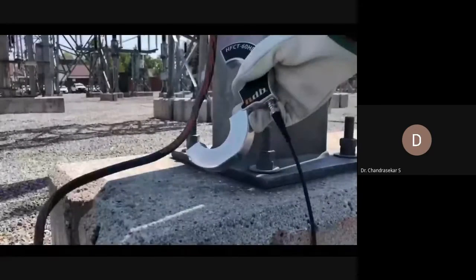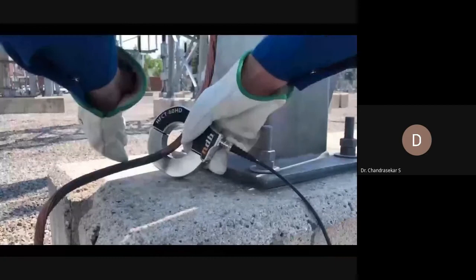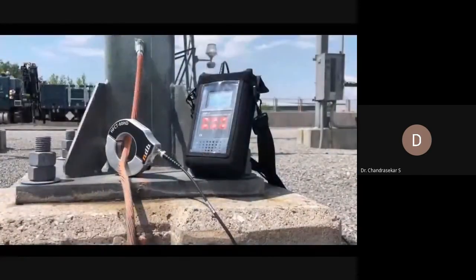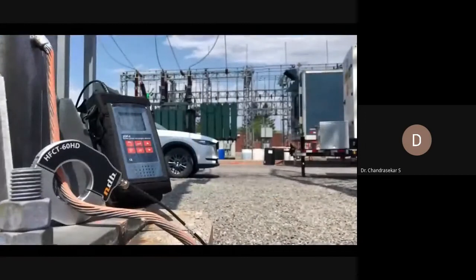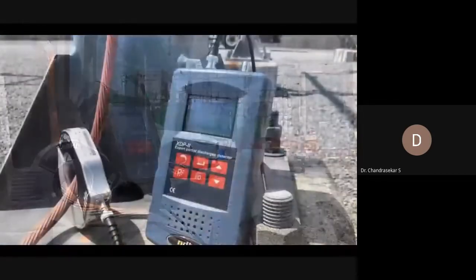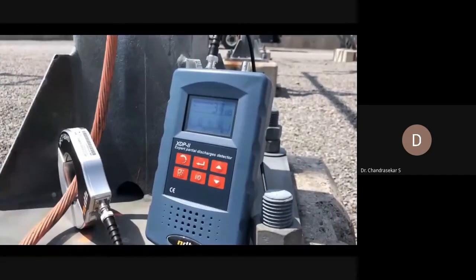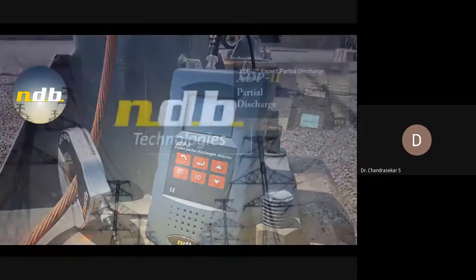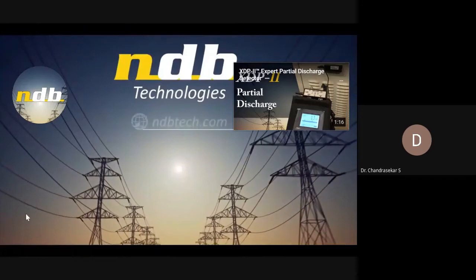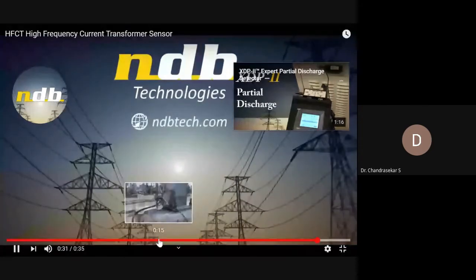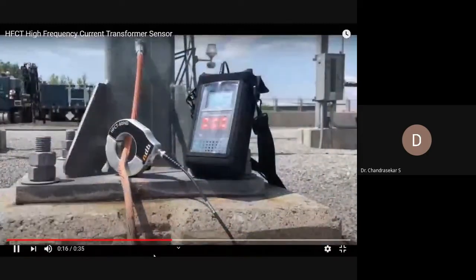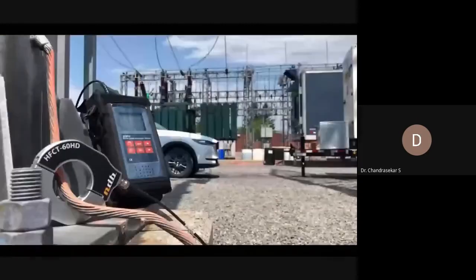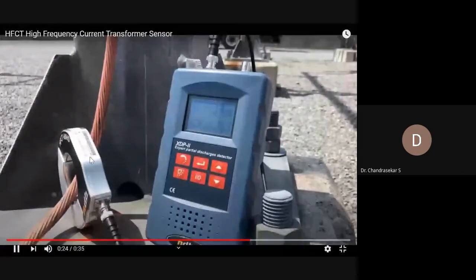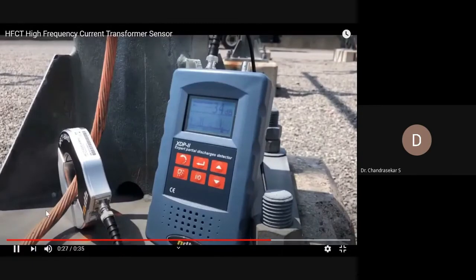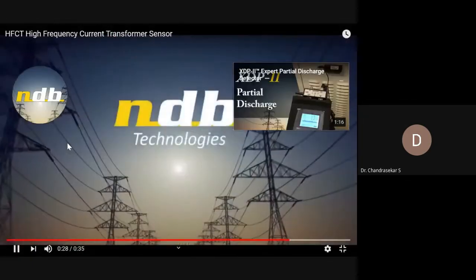Okay. So this is the high frequency current transformer sensor, which is connected in the ground lead of the terminal, and then they are measuring the leakage current or partial discharge happening inside, and this is the partial discharge detector. Okay. So like this, it is a very simple connection. It's a split core type HFCT, therefore you can easily connect it in any ground lead. Okay. So this is a very advanced sensor which will operate in 50 megahertz bandwidth.